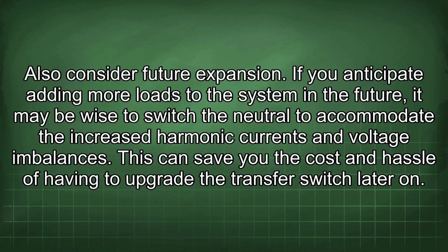Also consider future expansion. If you anticipate adding more loads to the system in the future, it may be wise to switch the neutral to accommodate the increased harmonic currents and voltage imbalances. This can save you the cost and hassle of having to upgrade the transfer switch later on.